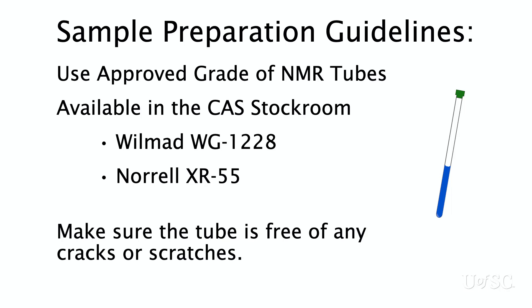Do not use tubes labeled high throughput or disposable. They can potentially damage the NMR probe because they may not be straight or may be oversized.